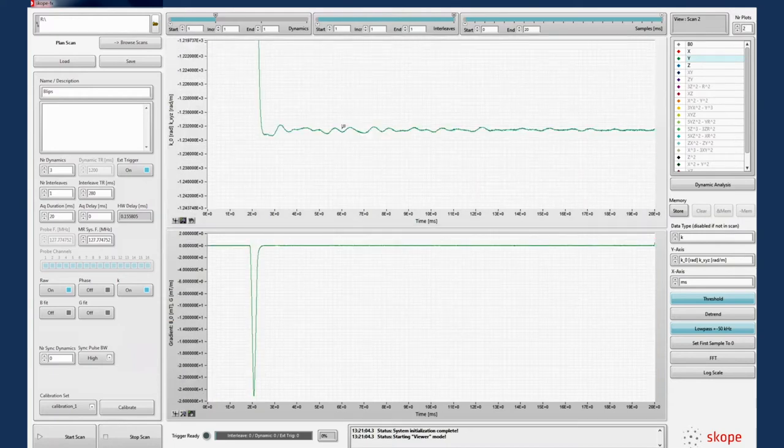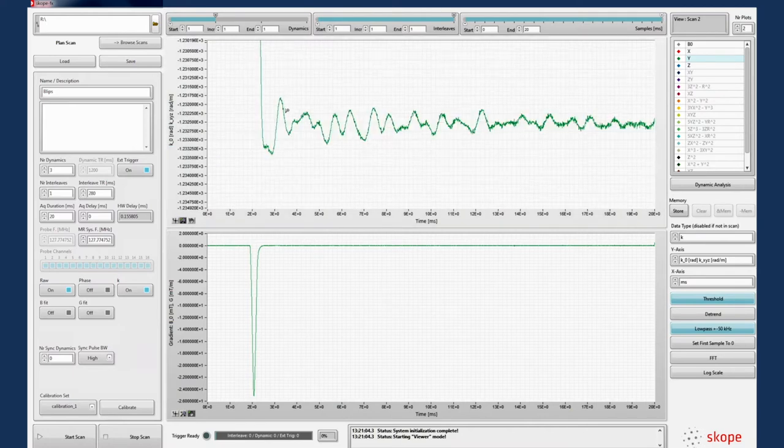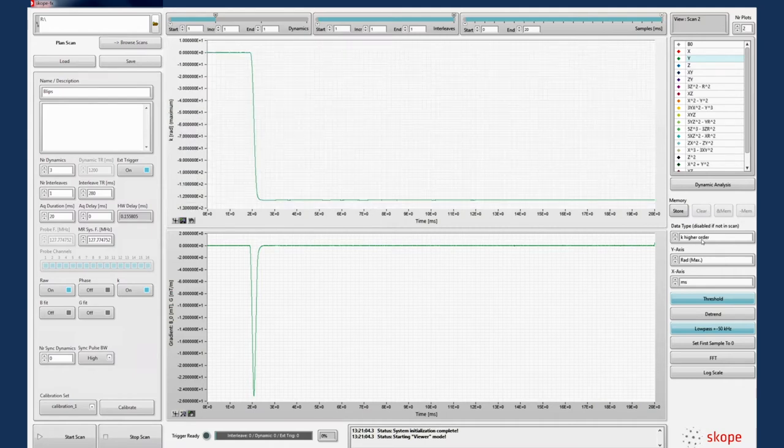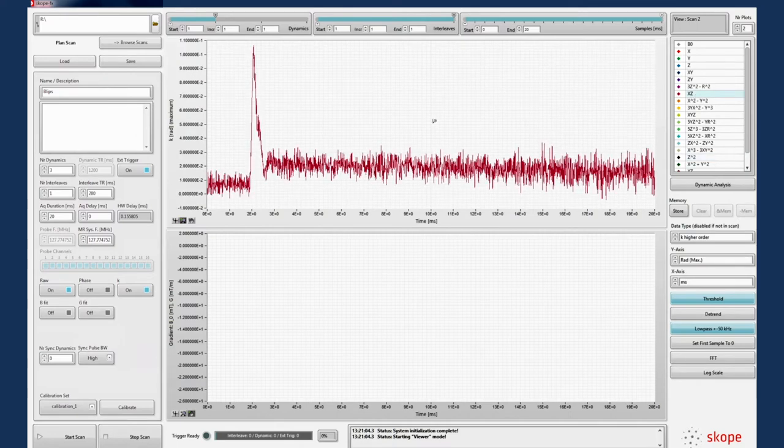The complete method for calculating a gradient impulse response function is outlined in a paper by Johanna Vannesjo in MRM 2016. Such measurements with the dynamic field camera allow for direct, fast and accurate characterisation of gradient and shim systems, such as frequency responses and higher order field dynamics.